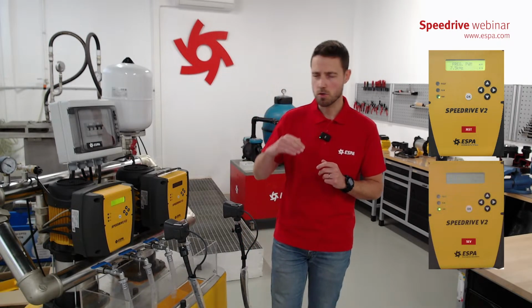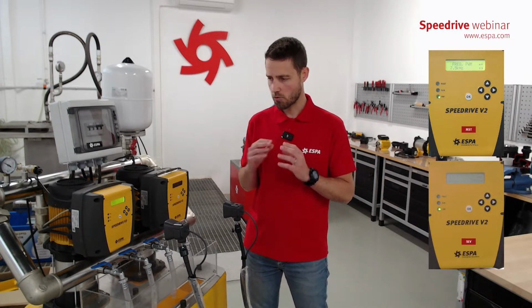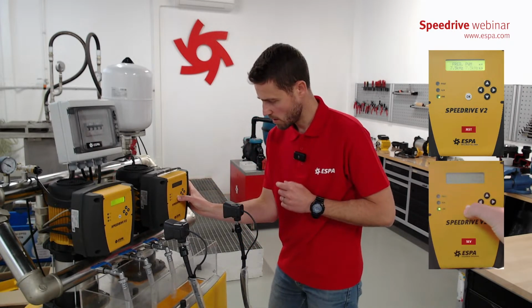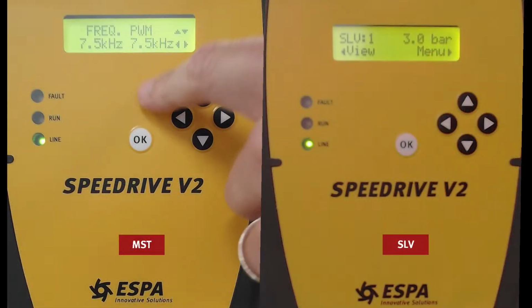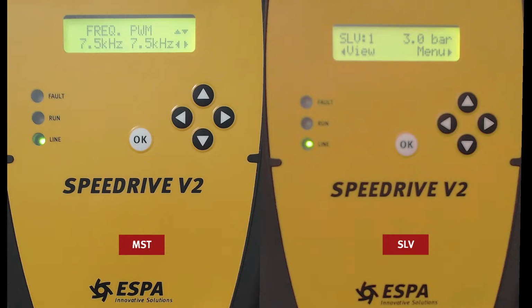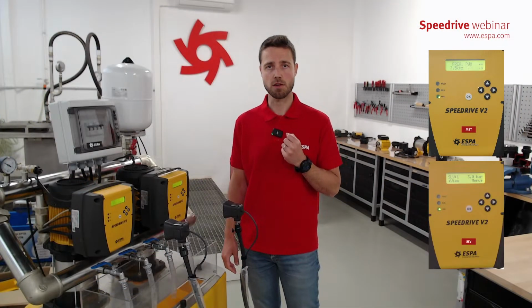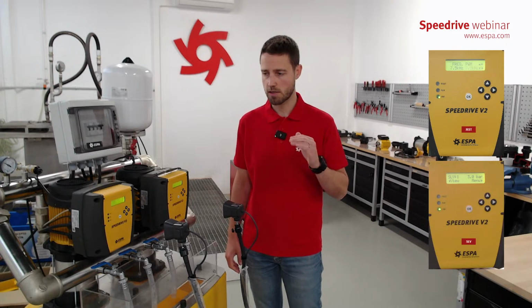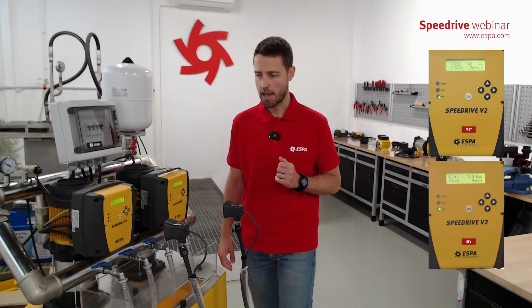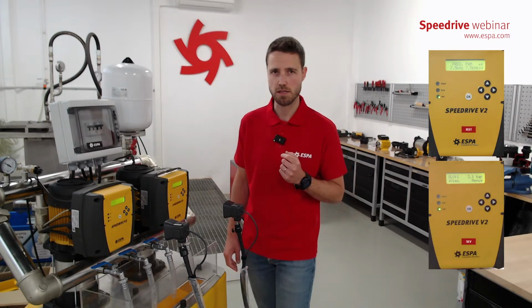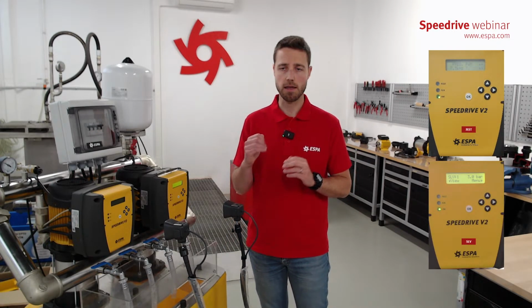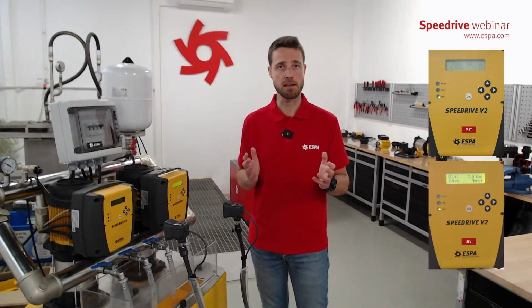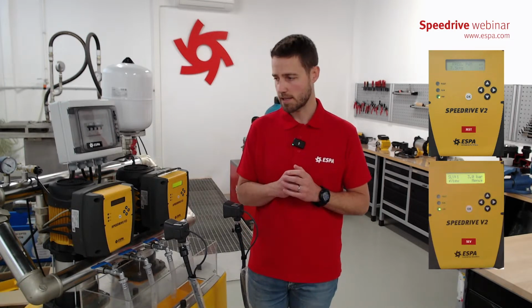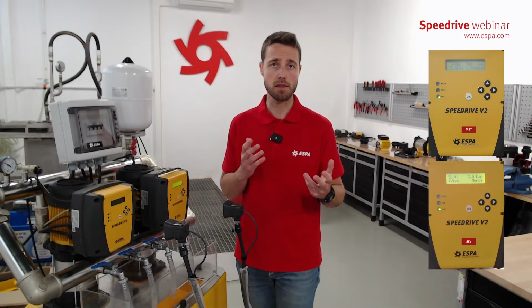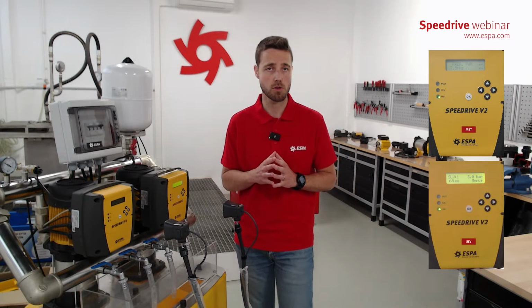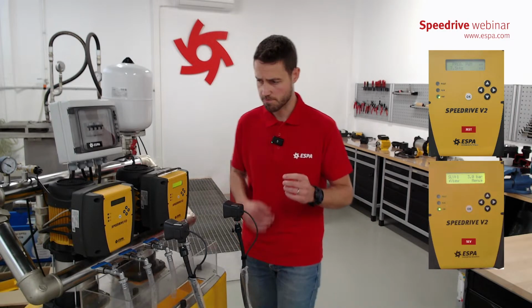If we go too high with the frequency of pulse width modulation, the Speedrive will go faster during the modulation, but maybe we will catch temperature. The temperature of the module will go too high and can be problematic for the frequency driver. As well, if the frequency is too high, maybe we will have electromagnetic interference. So this is also a setting that it's better not to manipulate, but if you do, or you can talk it over with us, we can solve it.